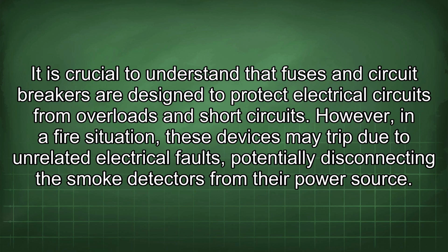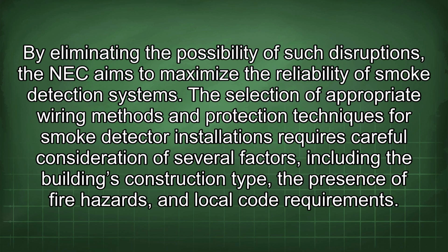It is crucial to understand that fuses and circuit breakers are designed to protect electrical circuits from overloads and short circuits. However, in a fire situation, these devices may trip due to unrelated electrical faults, potentially disconnecting the smoke detectors from their power source. By eliminating the possibility of such disruptions, the NEC aims to maximize the reliability of smoke detection systems. The selection of appropriate wiring methods and protection techniques for smoke detector installations requires careful consideration of several factors, including the building's construction type, the presence of fire hazards, and local code requirements.